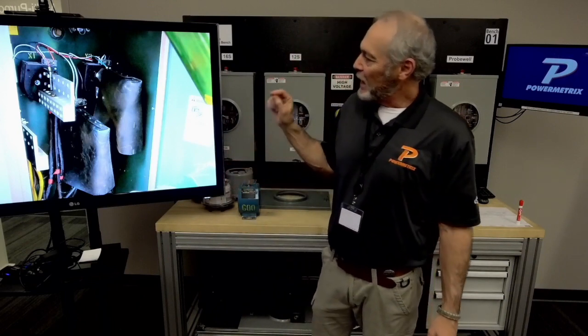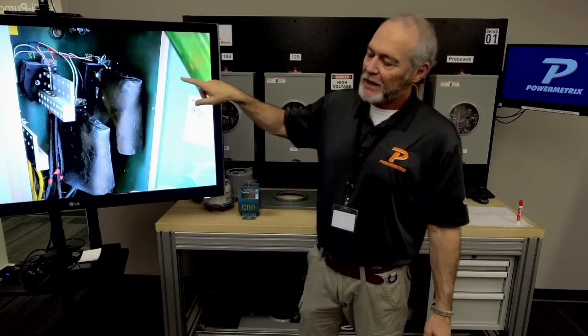But anyway, don't do what I do, do what I say. As far as the sleeves, here's another instance where, if they're supposed to have sleeves on all of those transformers and they don't, that's another thing to report as the eyes and ears of the utility. We had gone into a situation where they were supposed to have sleeves and didn't have them. Guys, for whatever reason, something happened, they took them off, didn't put them back, forgot them, whatever it is. Some guys think it's a pain in the neck to fool with them. I don't know why, but if it's supposed to have sleeves on and doesn't, make a note to put sleeves back on. Next time you're out in that area, you can stop by and put the sleeves on.